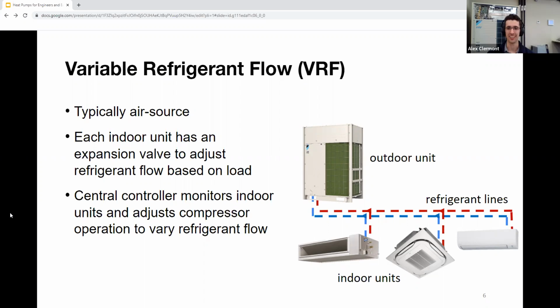And there's actually 2 different kinds of VRF. There's VRF heat pump and VRF heat recovery. Heat pump is also called a changeover system, and heat recovery is sometimes called a simultaneous system. What we're looking at here is actually a VRF heat pump system, where the entire system has to be in either heating or cooling. Now, each zone can modulate how much cooling it wants, but for the whole system to go into heating, all the zones will have to be in heating.